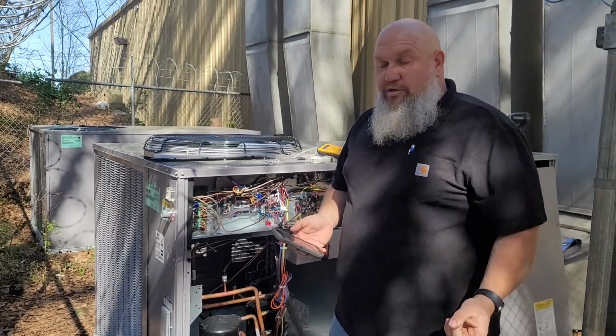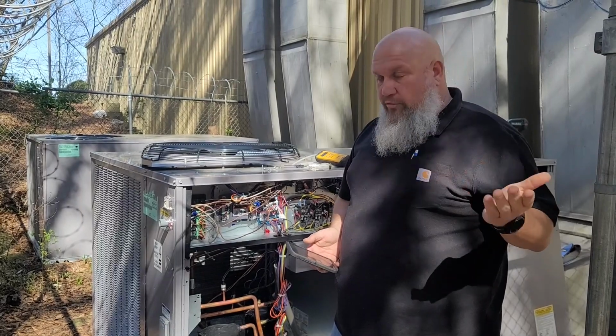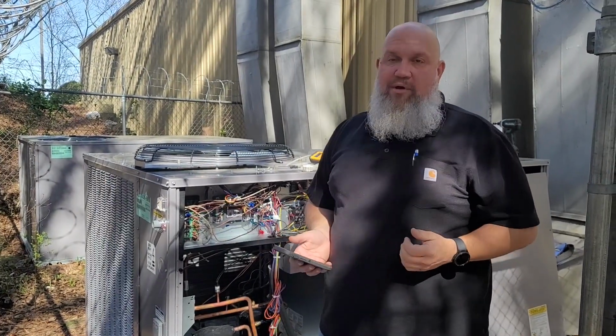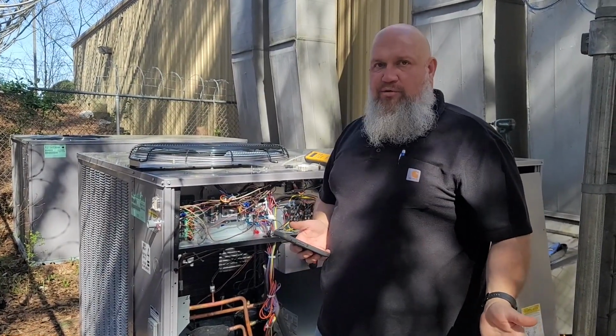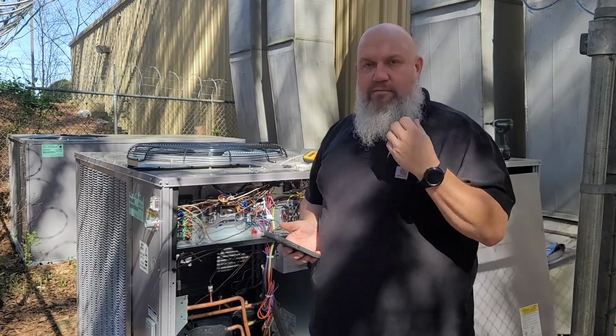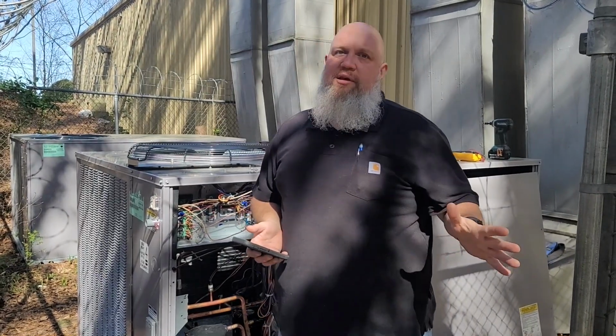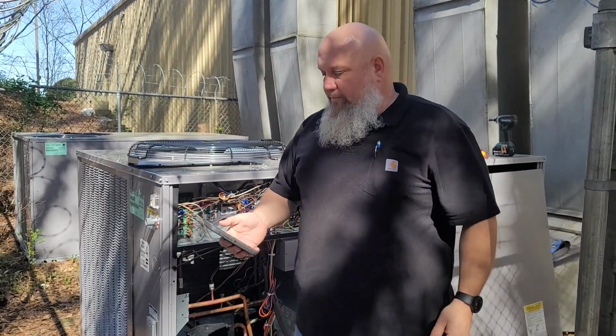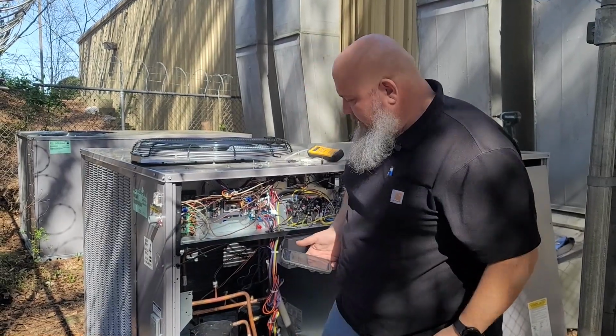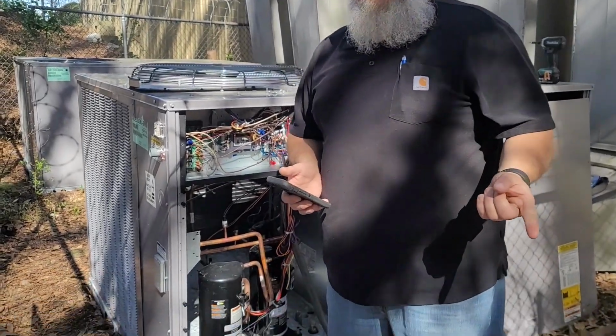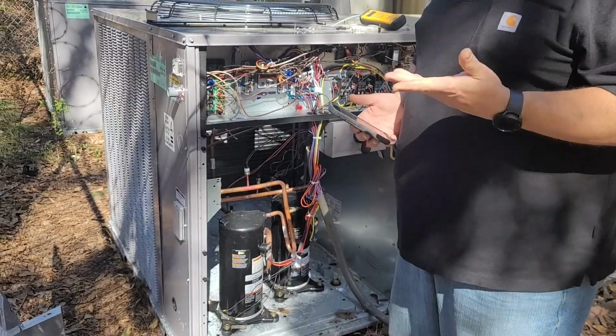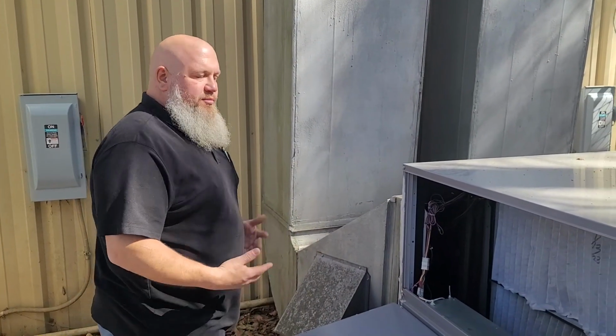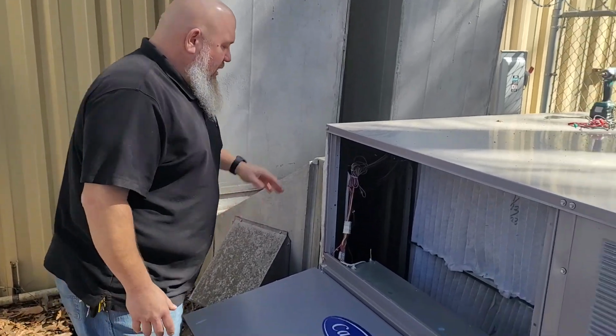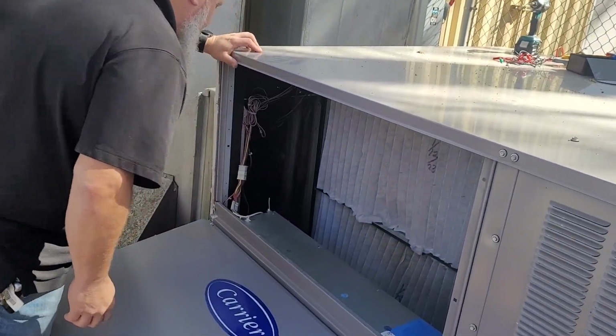And make sure that the thermostat's running, and in this case we have EMS. Make sure that EMS knows that the unit's here, they're communicating, and they're seeing all their sensors. And this unit has crankcase heaters. You got to make sure that those have power going to them and they're running while the unit's off. Part of the process, checking the filters, making sure everything looks good. Give it a once over.